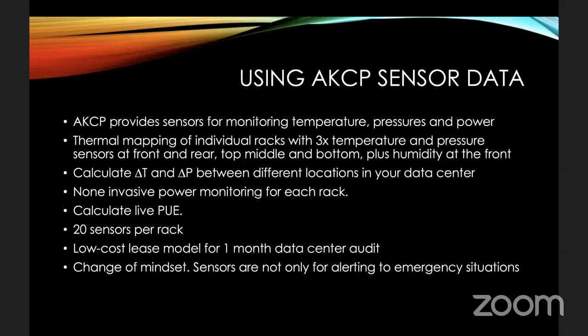After you've crashed your car, or your house has burnt down, that's when you think, I really should have had insurance. But nobody wants to pay for it up front. And that's kind of the same issue with the sensors. No one wants to pay for these sensors because it's just an insurance policy in case my server overheats. So do I need a sensor on every rack? Maybe I can put it every other rack. Maybe I don't need it on every rack or every other rack. Maybe I just need one in my cold aisle and that's enough because it's cheaper, right? One sensor in my cold aisle instead of one sensor per rack.